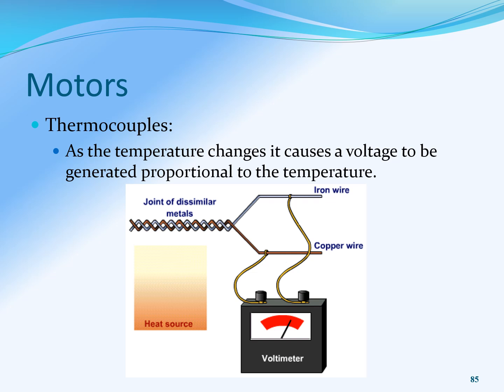So when the hot junction is exposed to heat, a temperature gradient is created between the hot junction and the other end of the couple. This creates a difference in the electron energy level of the two metals, which generates a small voltage. That small voltage is then generated on the cold end. And so that's how this thermocouple is reading the temperature.